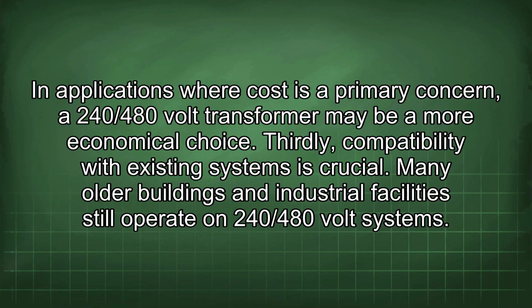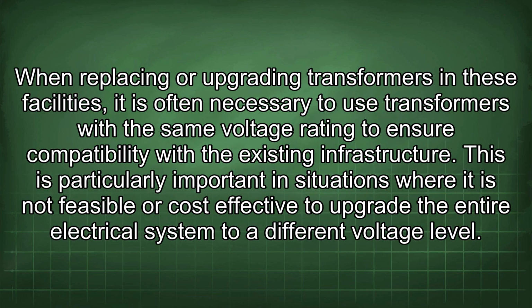Thirdly, compatibility with existing systems is crucial. Many older buildings and industrial facilities still operate on 240/480 volt systems. When replacing or upgrading transformers in these facilities, it is often necessary to use transformers with the same voltage rating to ensure compatibility with the existing infrastructure. This is particularly important in situations where it is not feasible or cost-effective to upgrade the entire electrical system to a different voltage level.